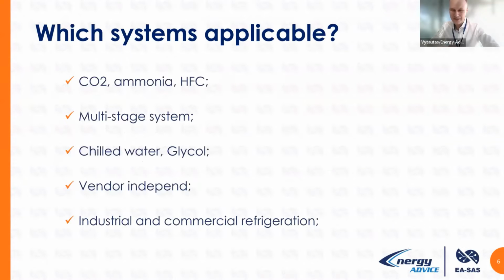In what kind of systems is our solution applicable? In fact, we have references for CO2, ammonia and Freon systems. We have experience with single-stage and multi-stage systems. We have experience with chilled water and glycol, where the machine is producing cold chilled water. We work with many types of vendors, so we can say that we are vendor independent, and it's applicable to industrial and commercial refrigeration. Today we more or less focus on industrial and commercial because it has the highest cooling capacity and the highest installed electrical capacity, it is where you have the highest expenses, and it could give you a very good ROI in a very short term.